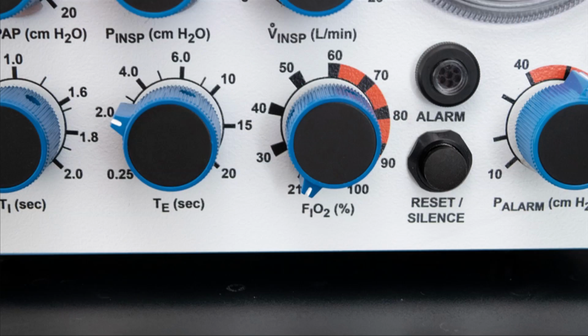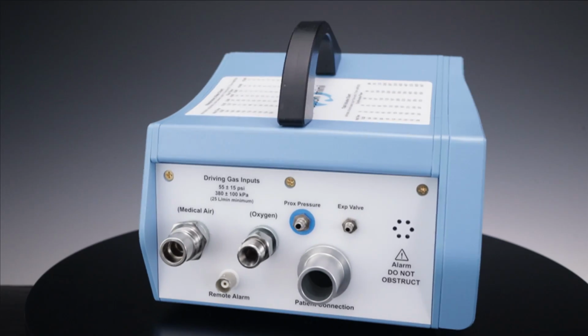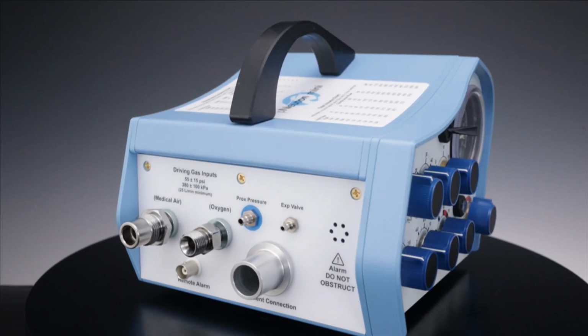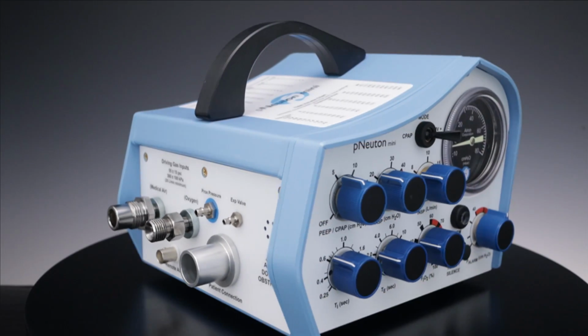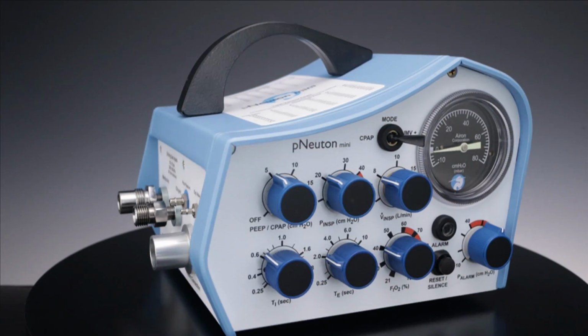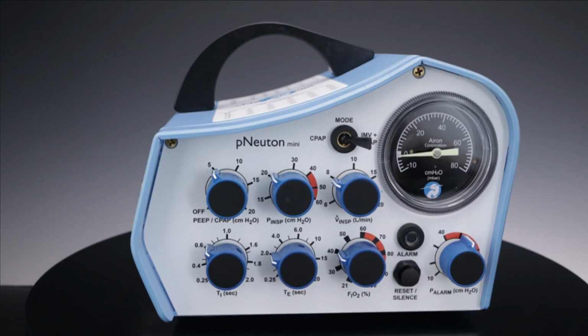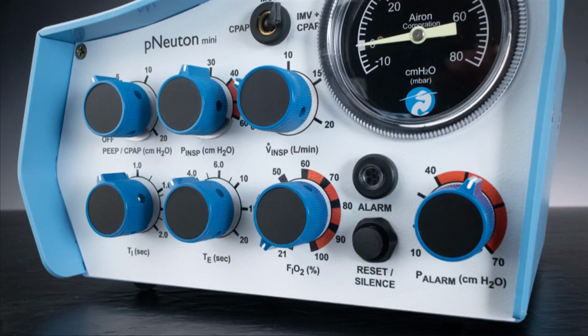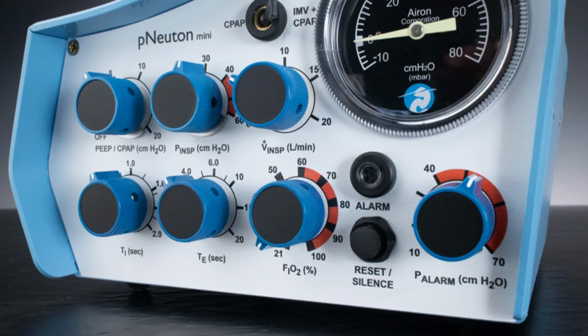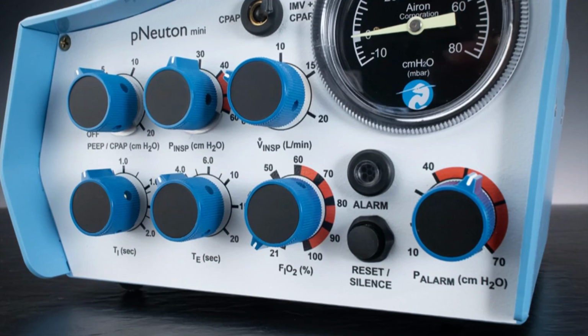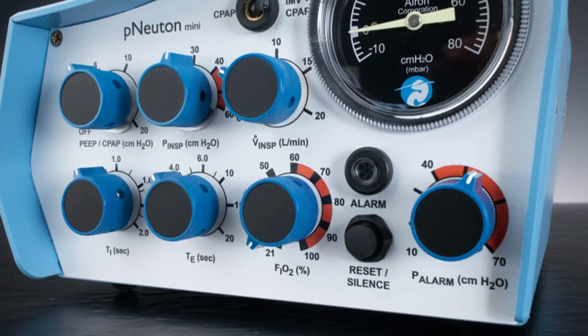The oxygen control, FiO2, sets the level of oxygen delivered to the patient. The calibrated range is 21% to 100% oxygen, plus or minus 3%. The ventilator uses an internal oxygen air mixing system, which provides the continuous flow into the patient circuit. Mandatory and spontaneous breaths are at the set oxygen percentage. Audible visual alarms. Next to the oxygen control are the features for the audible and visual alarms, the alarm visual indicator and alarm reset silence button.